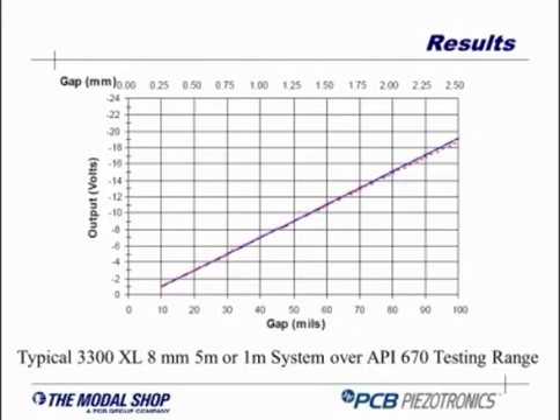But a very interesting capability of the 900D is it also allows you to do a dynamic test of the prox probe. I could easily set up my prox probe halfway through, like 1.5 millimeters from the target, then turn my shaker on at, say, 50 or 60 hertz, put a certain amplitude of vibration there, and watch the AC output - that simulates what you'd see in the real world with a shaft vibrating at that same level.